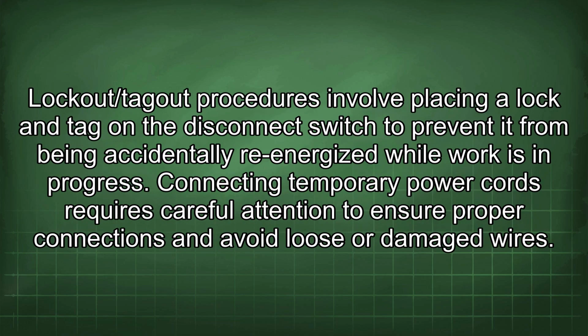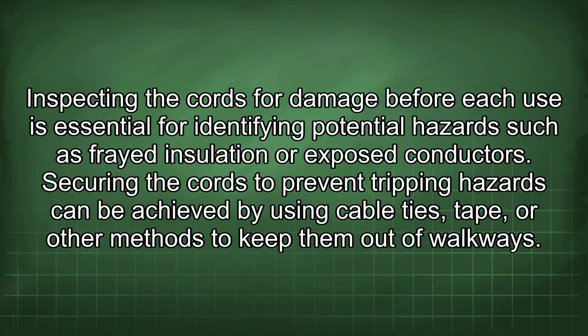Lockout/tagout procedures involve placing a lock and tag on the disconnect switch to prevent it from being accidentally re-energized while work is in progress. Connecting temporary power cords requires careful attention to ensure proper connections and avoid loose or damaged wires. Inspecting the cords for damage before each use is essential for identifying potential hazards such as frayed insulation or exposed conductors.